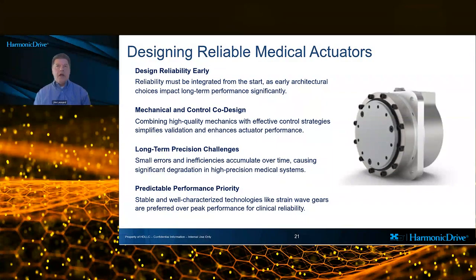So, designing reliable medical actuators. Several consistent lessons emerge when designing servo gear trains and actuators for high reliability medical systems. First, reliability must be designed in from the beginning rather than added during validation. Architectural choices made early have the greatest impact on long-term performance. And second, mechanical and control co-design is essential. High-quality mechanics simplify control and reduce validation burden, while well-designed control strategies can fully exploit mechanical advantages.